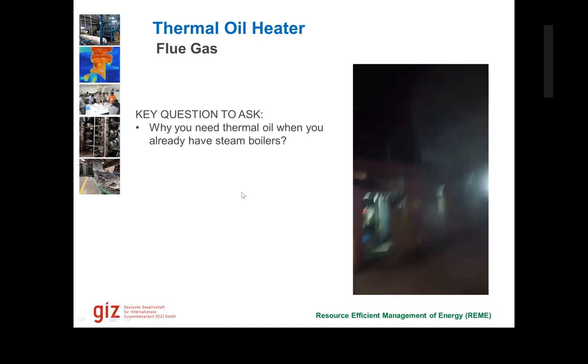And when you're using steam, there's also condensing that takes place. We do not want any condensing taking place in these kinds of processes, where we're using drying. So that is also one of the reasons. Also, as you said correctly, to be able to exchange this much amount of heat that we're using with thermal oil, we need very high pressure steam, and we might need more energy in steam than we're using for the thermal oil.